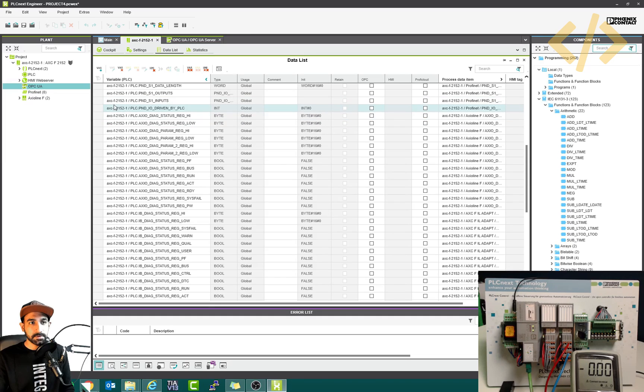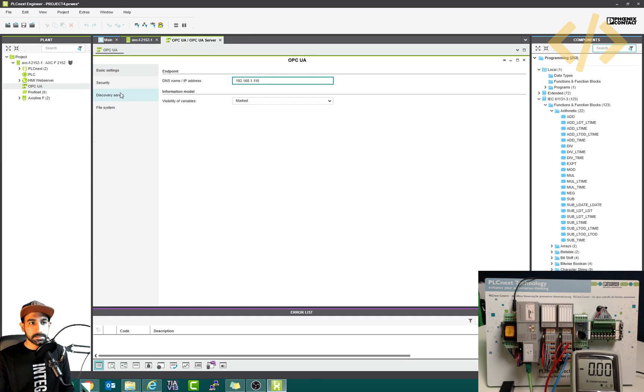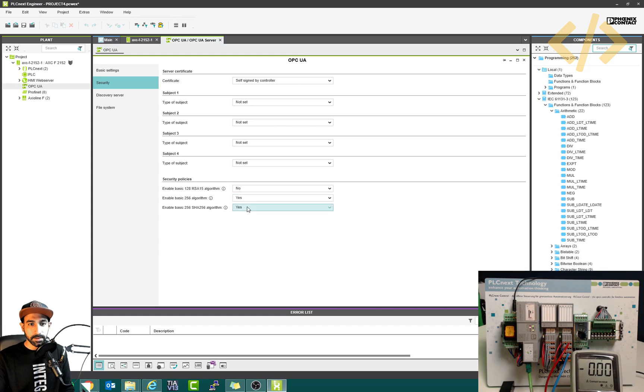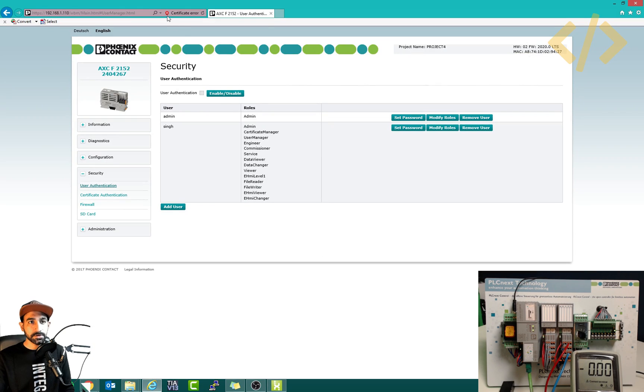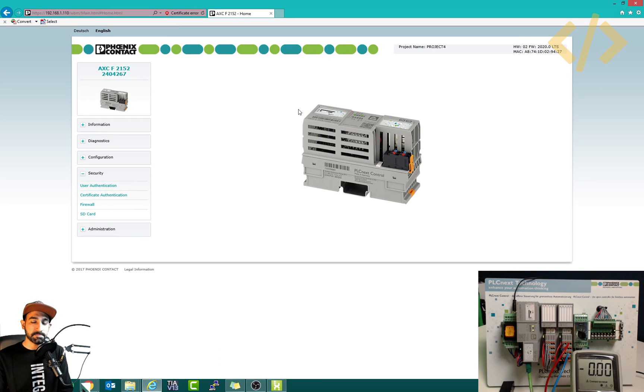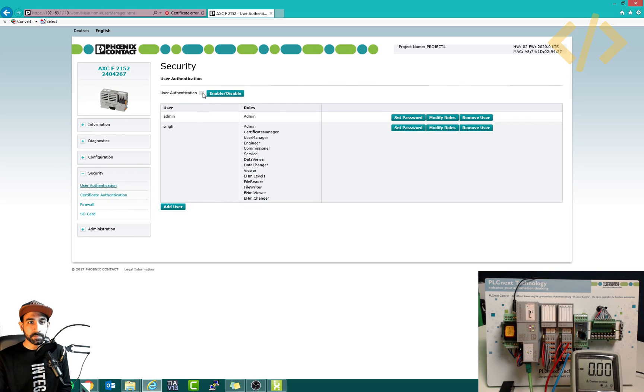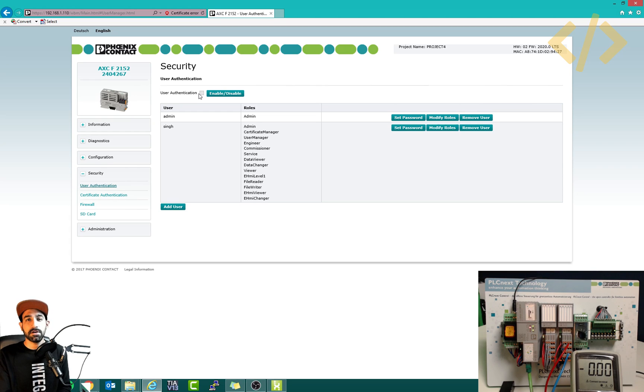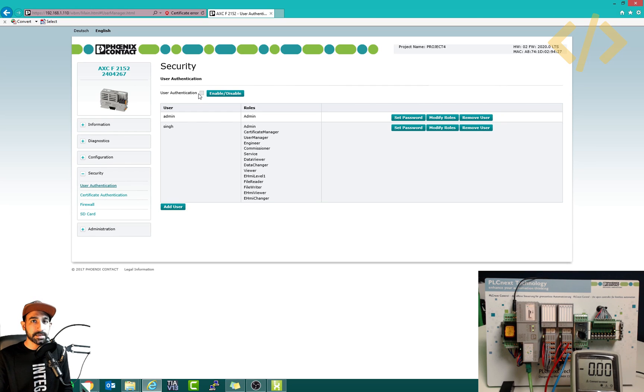One more thing in OPC UA — there are some security settings. I have set some to 'no' and there's another setting I disabled. If you go to your IP address and type WBM next to it and press Enter, you'll come to this screen and may need to log in. I have disabled the authorization, so under user authentication, I disabled that — meaning I don't have to enter an ID and password while connecting to OPC UA. Since I'm working at home on a local network not connected to the internet, I'm safe. In your case, it may be enabled and you'll need to enter credentials.